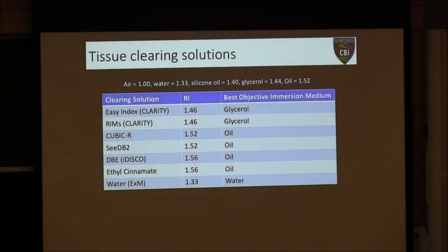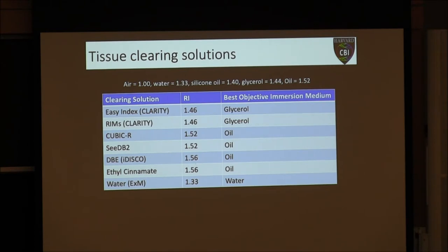The same thing goes for tissue clearing solutions — these can have refractive indices all over the place. The nice thing is we actually have some objectives that are really well matched to at least the CLARITY-type solutions. And for anyone doing expansion microscopy, water-immersion or water-dipping objectives work fantastically for those.